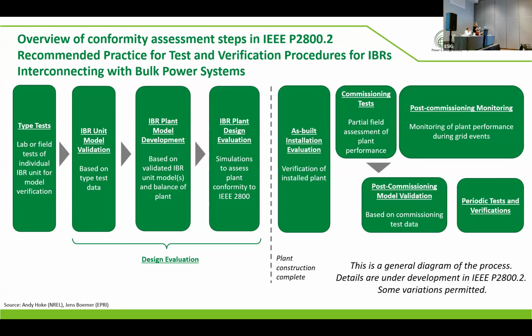Why am I saying this in a kind of complicated way? Because 2800 applies at the POI. And so you cannot actually have a 2800 certified inverter, because you can certify an inverter all you want, but depending on how your plant is designed, the performance you'll see at the POI may be different. So manufacturers cannot guarantee that the inverter they sell will provide whatever you want at the POI. But they type test taking these requirements into account, and the goal of this type test is also to produce a unit model that has been validated. And then this unit model is used to develop a plant model.